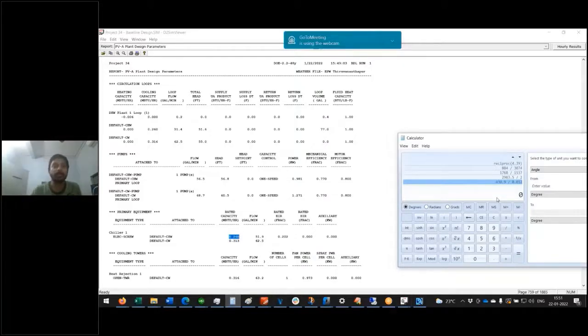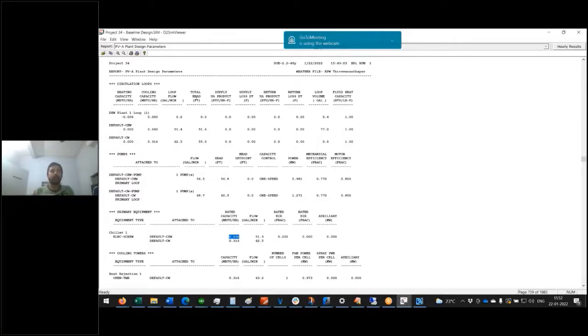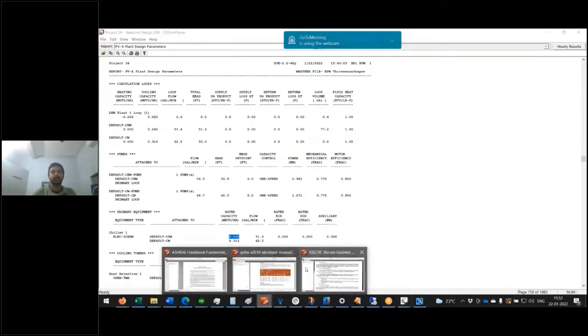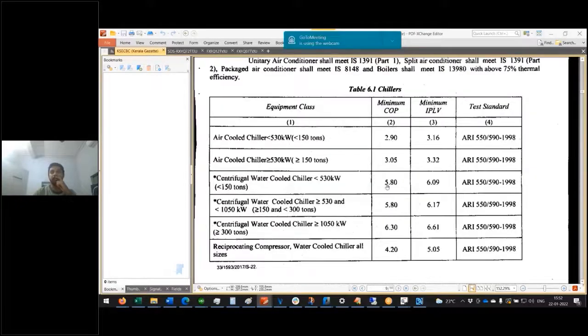So 260,000 per 12,000, that's 21 tons. Okay, that is how under PVA, plant design parameters, you will get the chiller capacity. Now one more thing you have to also remember is that when manufacturers give you the EER, energy efficiency ratio, or COP, or whatever is defined over here in KS ECBC, please note that these COP are under standard test conditions and not design conditions.